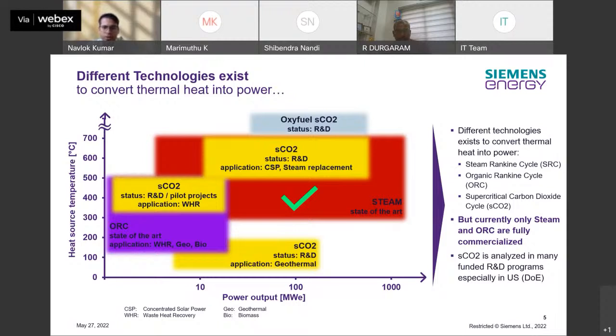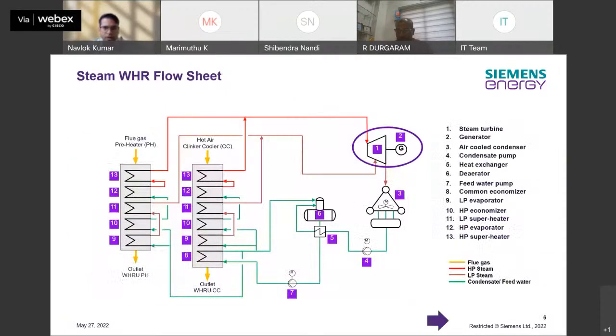However, due to paucity of time, we will limit ourselves to the most widely used technology, that is steam Rankine cycle, which consists of steam boiler and industrial steam turbine. This is a process flow diagram for typical waste heat recovery system using steam Rankine cycle. It consists of a steam turbine, a generator, air or water cooled condenser, WHR boilers, and other process and mechanical auxiliaries. While all these components play a significant role in overall plant performance and availability, the two most crucial and performance governing components are the industrial steam turbine and the waste heat recovery boilers.